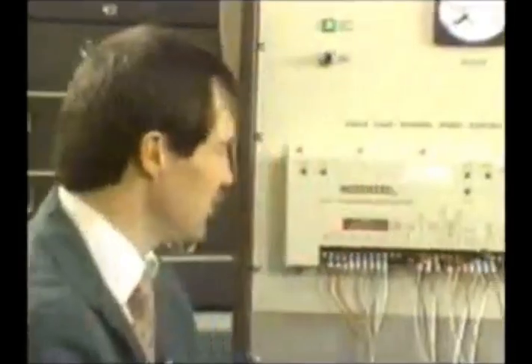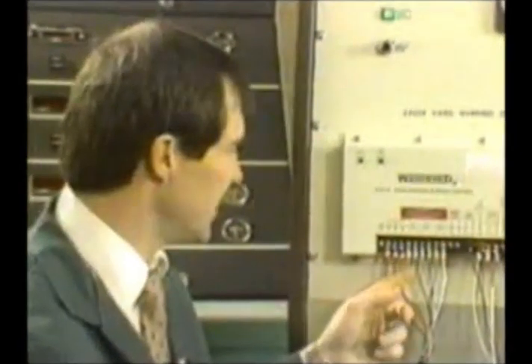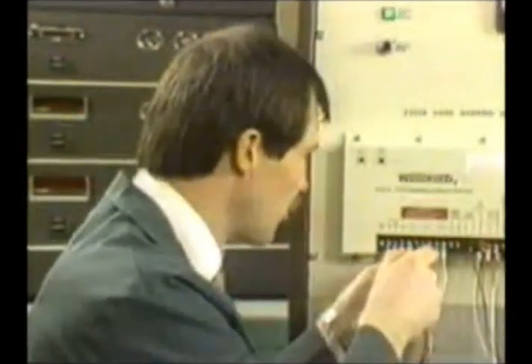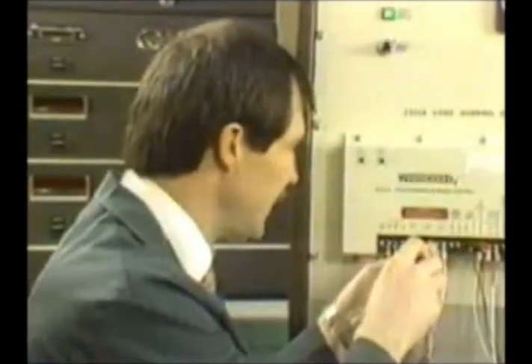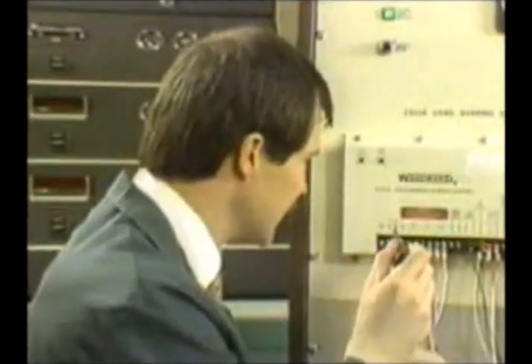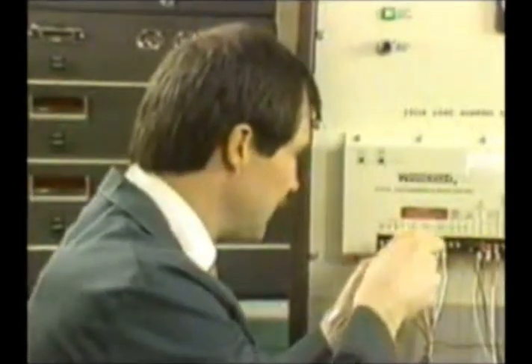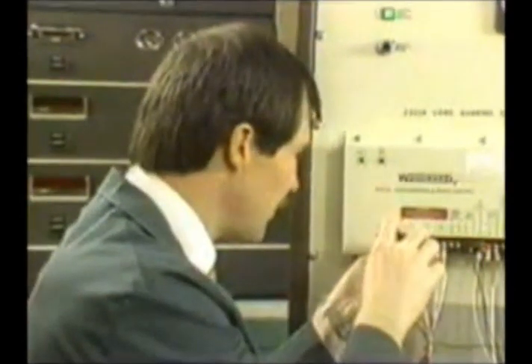Now what I need you to do, I need you to connect terminal 5, which is the A phase minus side of the CT, to terminal 4. So what we're doing, we're going to short out the A phase. Let me disconnect that. Loosen up terminal 4 here.